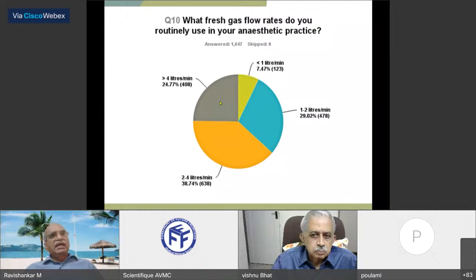Okay, so that is one. And how can you conserve? Here we are absorbing the carbon dioxide by using carbon dioxide absorbers so that carbon dioxide is not emitted out. And at the end of the case, many machines now are coming up with agent absorbents with activated charcoal filters. They absorb the agent before the gas is sent out into the atmosphere. So the agent also is trapped inside those filters, and those filters can be reactivated at a later place.